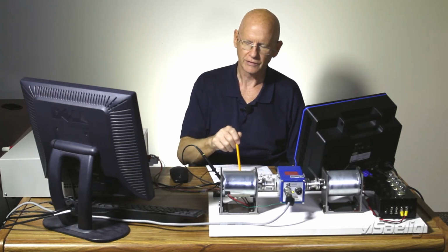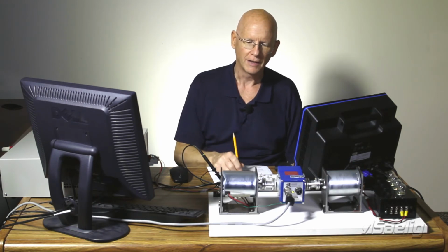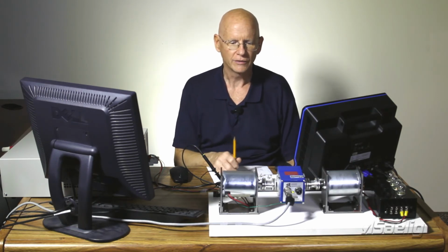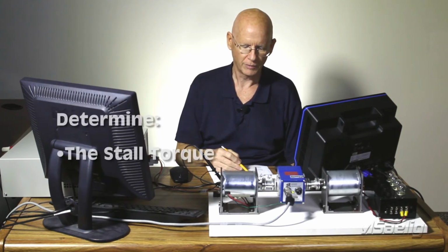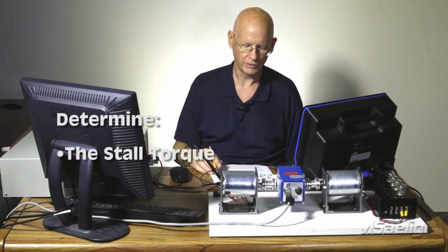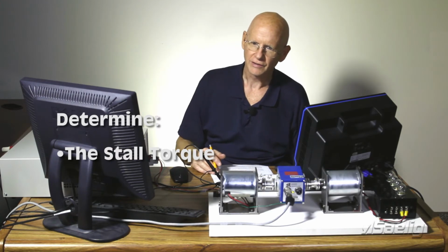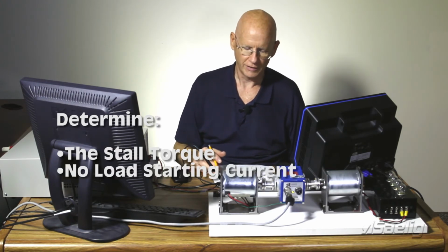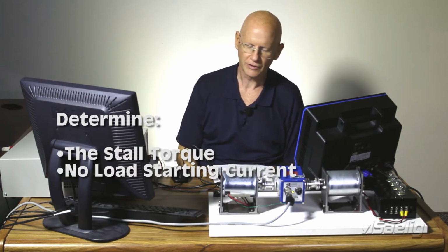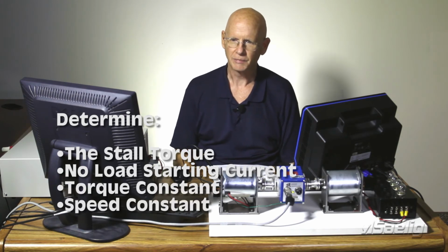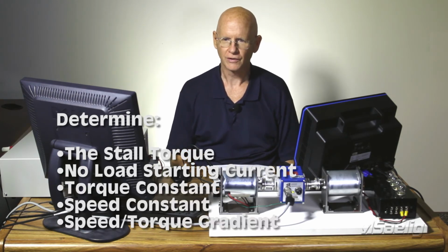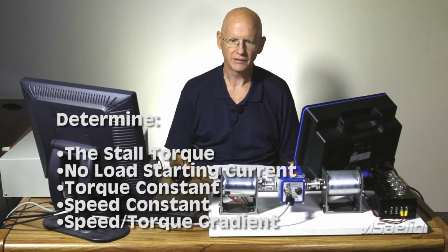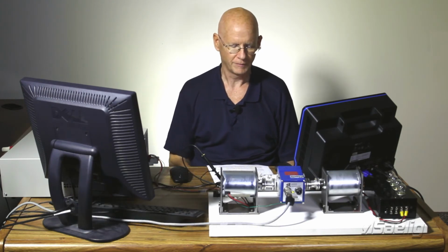And we're going to look at the current and the torque numbers while it's doing that. One of the things we're going to do is to determine what the stall torque is on this motor. We're going to take a look at the no load starting current, and we're going to determine torque constant, speed constant, and speed torque gradient from the information that we get from the torque transducer.